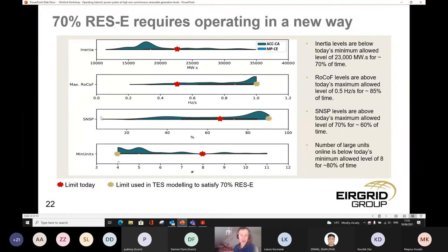And then on the SNSP limit, so currently 70%, trialing 75% at the minute, but the analysis shows we need to be getting that up to as close to I'd say 100% as we can get to be able to accommodate all this wind on the system.